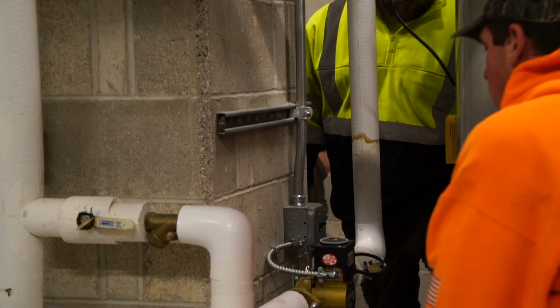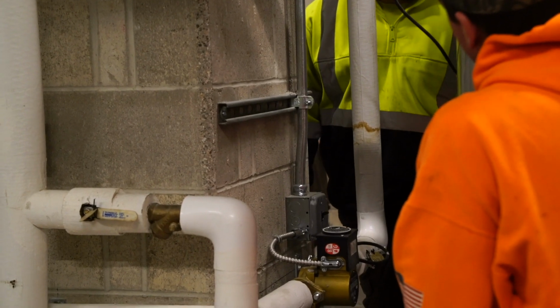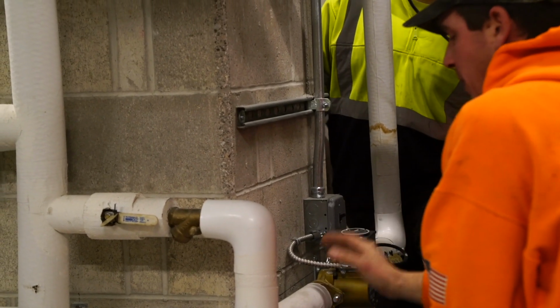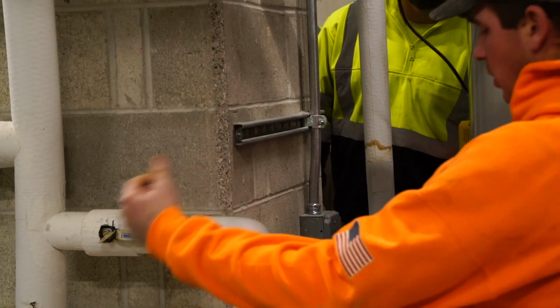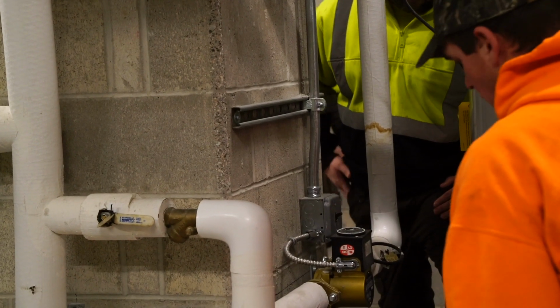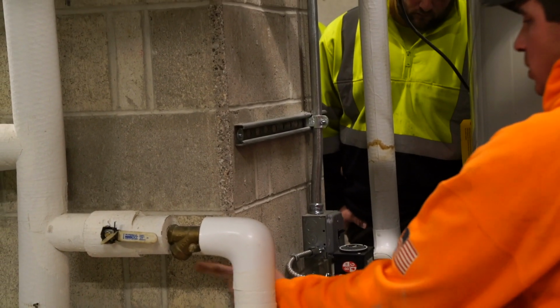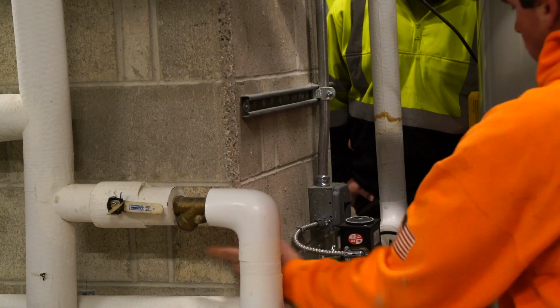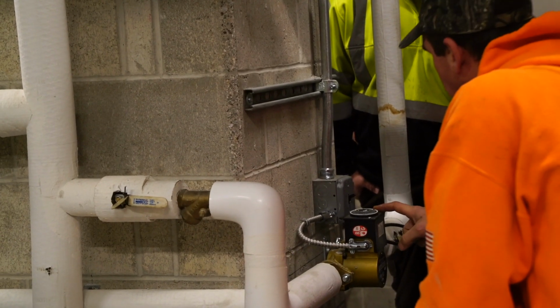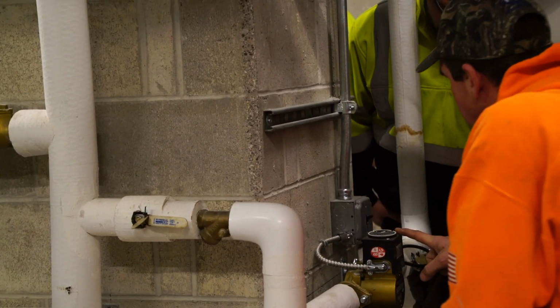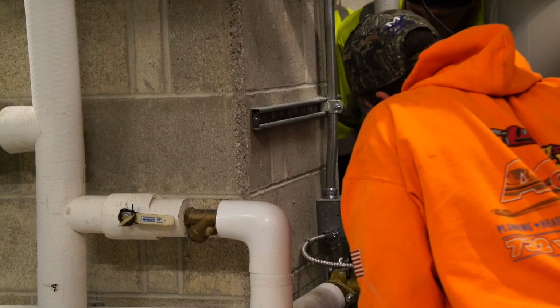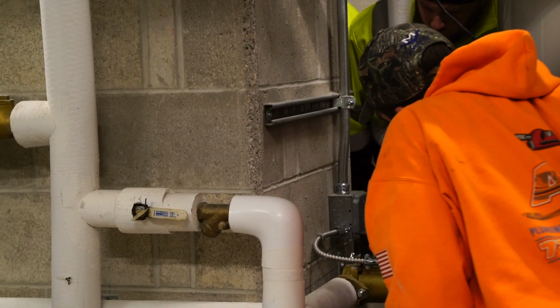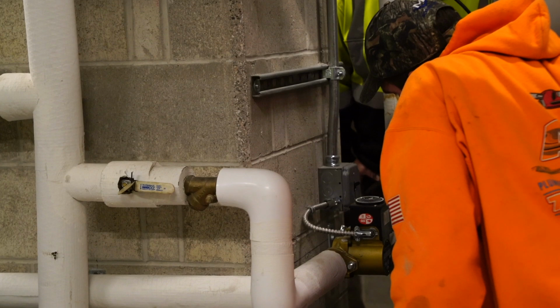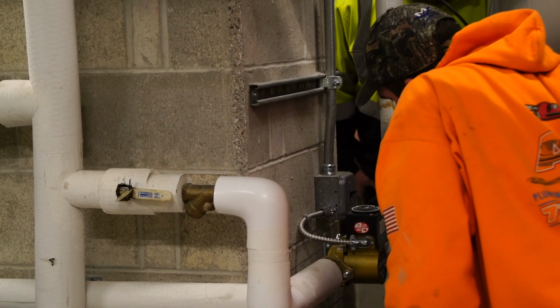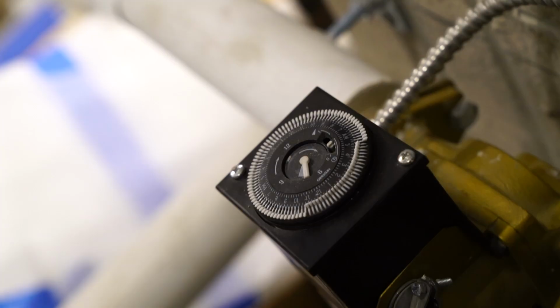So this is your recirculating pump. This is circulating the hot water throughout the building, pumping it back in. Some of it dumps back into your hot water heater. And like I said, some of it goes into your mixing valve. Timer set on top. I basically have it set for 5 a.m. to 11 o'clock at night.